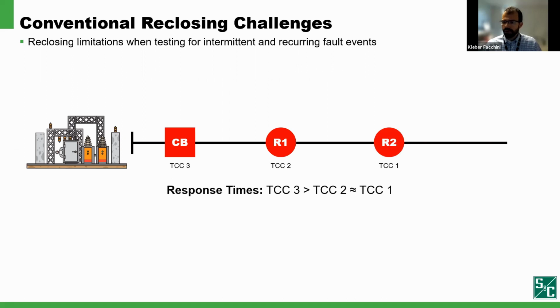As a last example, one more example here with using conventional reclosing, let's look at a possible situation when the midline reclosers are not coordinated. The circuit breaker is set to a lower curve than R1, and R1 and R2 are set with the same TCC curve, potentially due to coordination limitations on those devices. And in this situation, there is a great chance that faults happening downstream of R2 will trip both R1 and R2. So let's look quickly through this example.